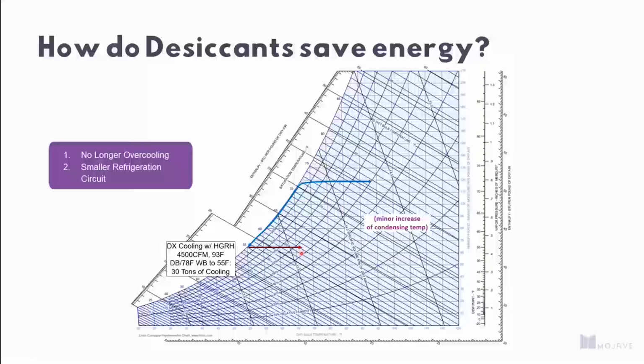Now, this is fundamentally an inefficient path of operation. When you cross enthalpy lines, you're doing work with a system. And when you're doing work, you use energy. So basically, in this situation, crossing between this enthalpy line and this enthalpy line, you're doing work that you don't want to do because it's overcooling the air just to reheat it back up to temperature. You're wasting energy trying to get the moisture out of the air and requiring a bunch of additional capacity to do that.